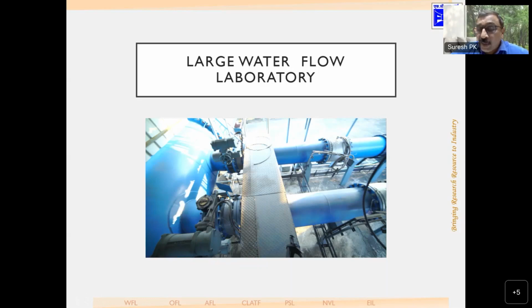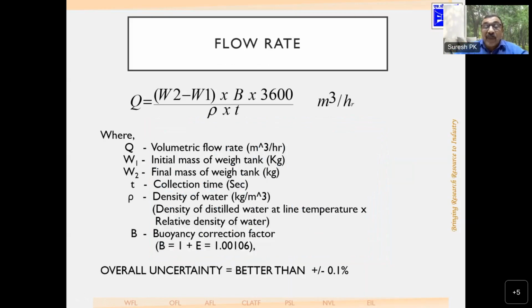The master meter method is generally used for flow meters of larger sizes, and this laboratory can go up to 15,000 meter cube per hour. Flow meter sizes up to 3,000 were calibrated in this laboratory. But of course, as far as the 3,000 meter is concerned, 15,000 is not a huge flow rate. But in our country, this is the biggest available. Therefore, one has to be satisfied with what is available rather than looking for something which is not available.